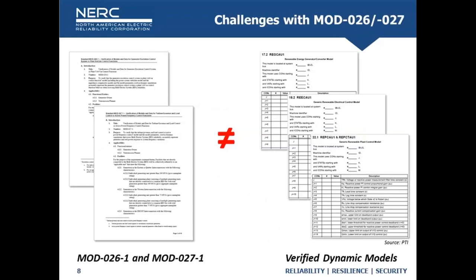So regarding that topic, put really frankly, and this was identified by the IRPTF subgroup that's been doing a standard review that I'll talk more about tomorrow, compliance with Mod 26 and 27 does not mean you have a dynamic model that is verified, quote unquote verified, meaning I can trust the large disturbance behavior of that plant. I can easily get a model that matches a 2% bump test to a voltage, a cap switch type event, and I don't have any parameters that are correct in terms of my large disturbance behavior, things like momentary cessation. So this is one of the issues why we have dynamic models that may be verified, may have the Mod 26, 27 compliance, but it doesn't mean the model's right. It doesn't mean that for a bolted three-phase fault out in the grid the unit's going to perform in the model as it does in reality. And I think that's one of the main challenges we have.